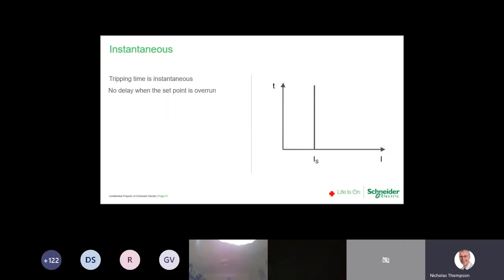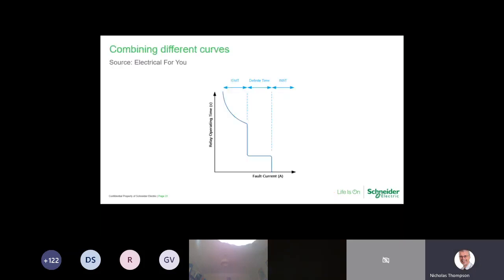The other one is instantaneous. So here we've got a set point. It could very well be 100 amps. So it will send a tripping signal to the circuit breaker instantaneously at 100 amps or above. And this is where the juggling now starts, because under various applications, you may decide to use 1, 2, or 3 curves as a combination. And we would have what we call 3 set points.